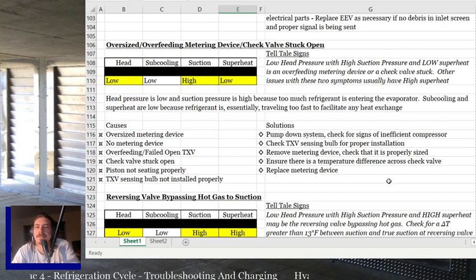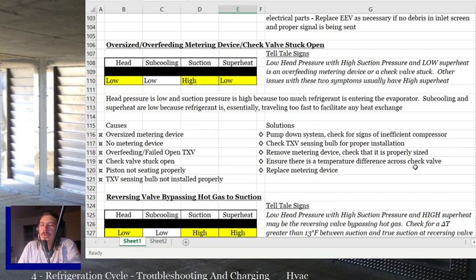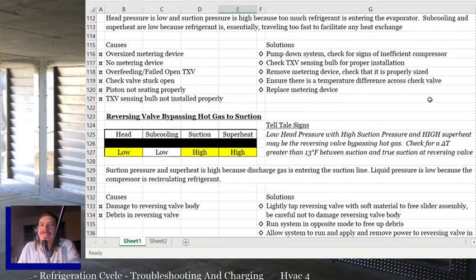And then the next thing is just replace the metering device, which is generally what you're going to be doing. You're either going to be fixing where the sensing bulb is at, or you're going to be replacing a metering device, or installing a metering device for the first time.